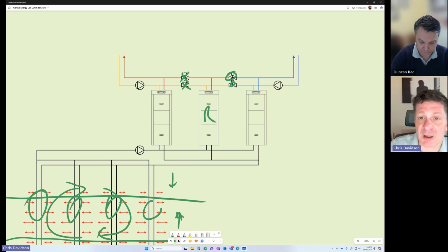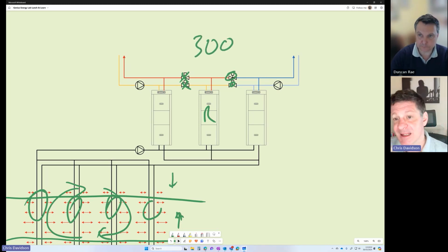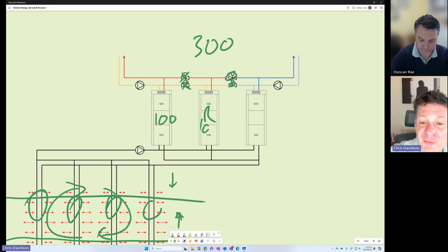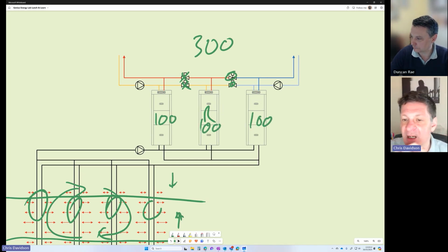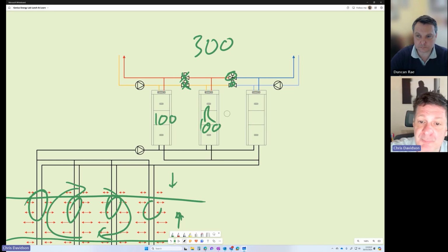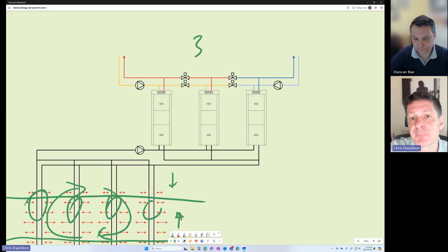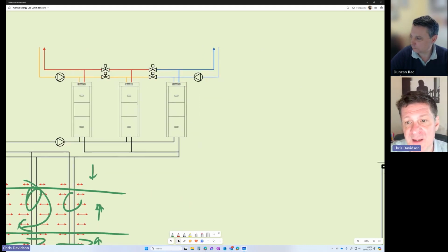If we've got a 300 kilowatt load here and we put 500 kilowatt heat pumps in there, we're going to be grossly oversized for the load. So we're really going to want 100 kilowatts or close to it, so we're accurately matching that load in the system. We've also got to understand what these systems can turn down to, because that 300 kilowatt peak heating load might actually translate to a 10 kilowatt heating load, and how do we cater for that with big 100 kilowatt heat pumps? And to illustrate that in a little bit more detail, let's think of a common mistake that's made in this regard.